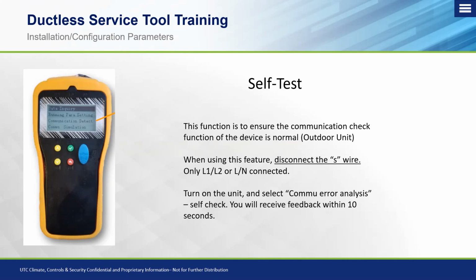Or if you're doing this from a preventative maintenance point of view, you can go through individual indoor units and make sure that everything is responding with the board properly. But chances are, if you're doing it on one zone, the other zones are going to be communicating properly. Otherwise, every one of those zones would probably have an E1 issue. But again, this is more so on the service side of things, but you're always more than welcome to use it on the preventative maintenance side to really be thorough.